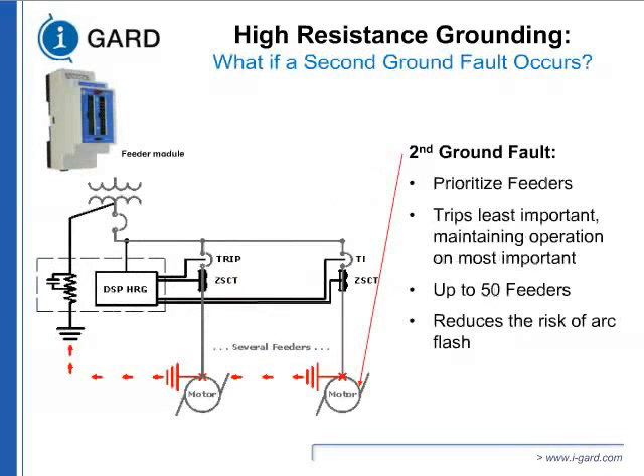Second ground fault happens. Now you're going to go phase-to-phase. I don't know how many of you who are listening had responsibility for the plants. I had a few plants under my responsibility. I was a technologist, and one of my main fears was that, for some reason, most of the ground faults happen on Friday after 5 o'clock when we don't have anybody to troubleshoot. And you are waiting till Monday with your fingers crossed, hoping a second fault does not happen.